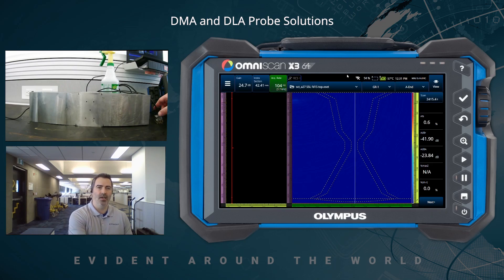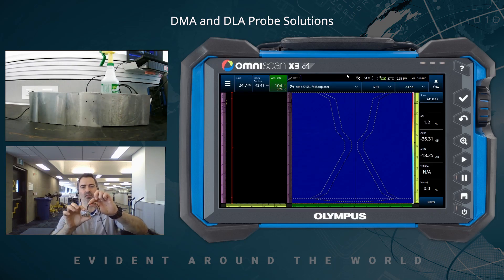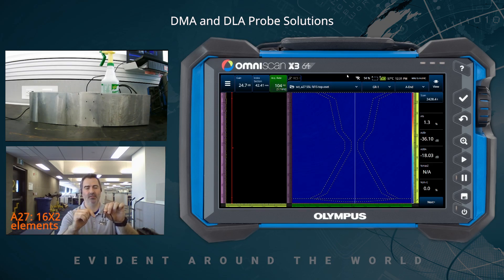I have three probe models with me today. First off, the A27 — that is a 4 MHz DMA, dual matrix array. In the active axis there are 16 elements, and on the passive axis, two elements. The pitch is one millimeter and the elevation is three times two, so six millimeters on the passive axis.